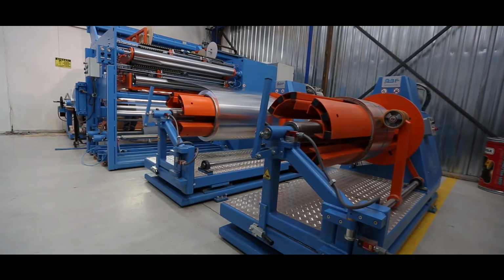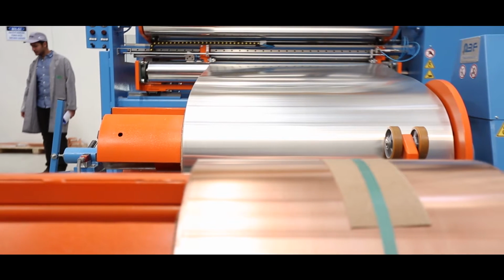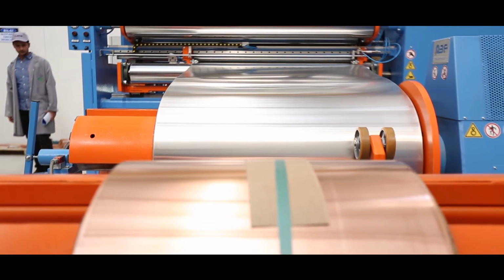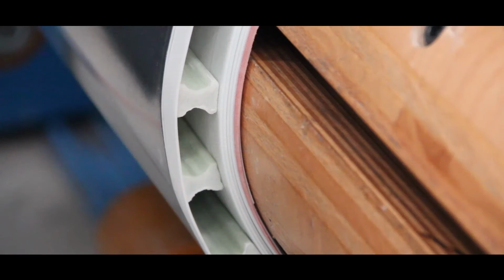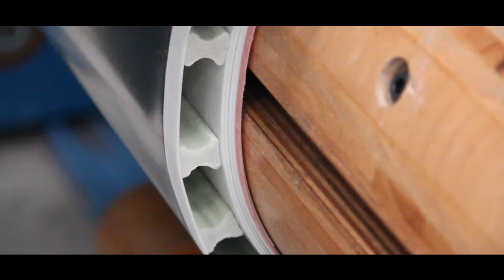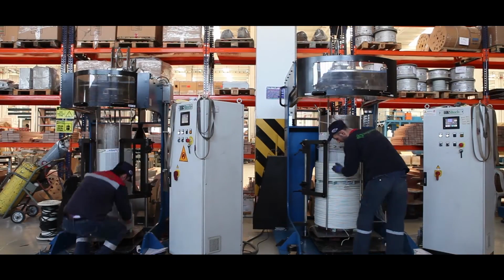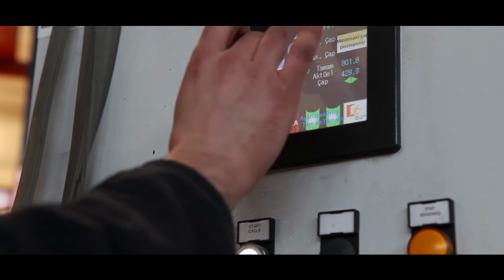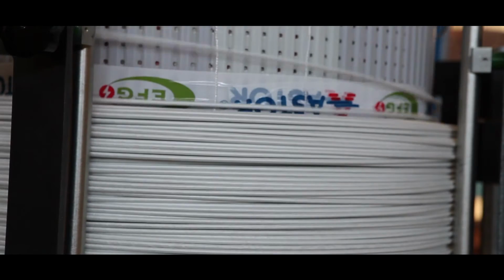Dry-type transformers. Tape winding technology, copper or aluminium tapes, are utilized for low-voltage windings depending upon the project design due to their technical advantages. Radial short-circuit forces are controlled through the utilization of special pre-resin impregnated material according to the desired isolation class between turns.